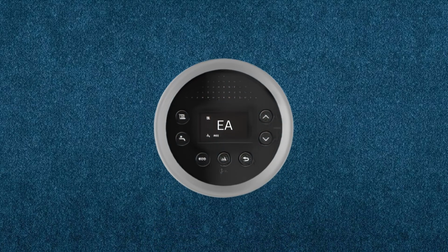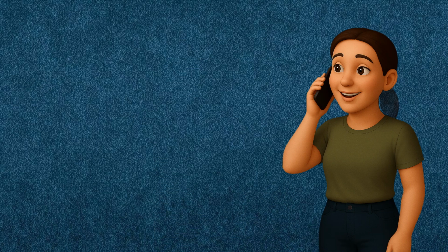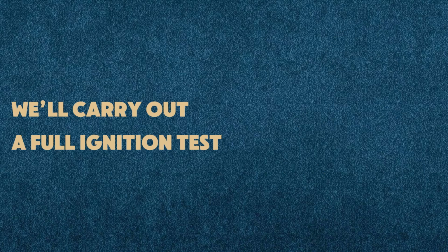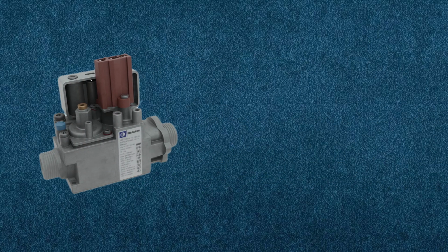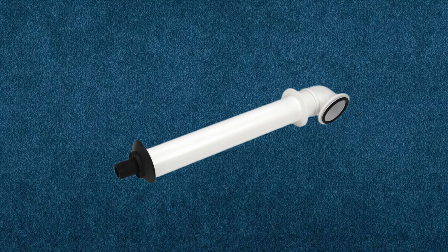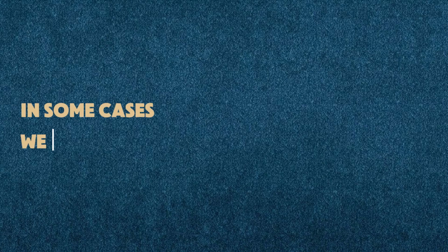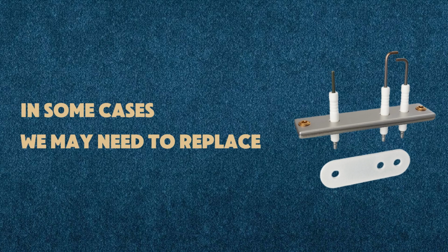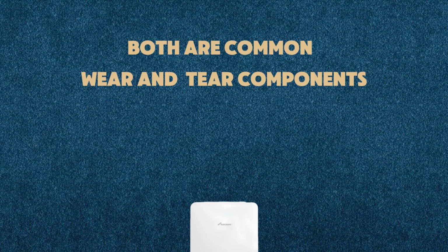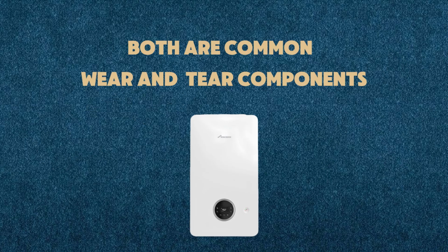If the EA fault keeps returning, it's time to contact BeFix. We'll carry out a full ignition test, inspect the electrodes and sensors, and verify that the gas valve and burner pressure are working correctly. We'll also ensure the flue and combustion are completely safe. In some cases, we may need to replace the ignition electrode or flame sensor. Both are common wear and tear components on older Worcester Bosch boilers.